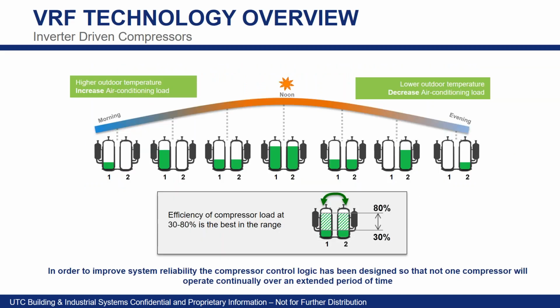Back to where we were here. Okay. Just a simple diagram here of how our compressors are loaded, right? High noon, we're going to be at full load, but then you're going to see as we taper down, we're going to start sharing that load, and that load is going to be shared through our compressors and where we're most efficient. You can see this diagram down here on the bottom. 30 to 80% is our sweet spot, and that's where our factory controls are going to try to keep our compressors running, because that's where we're most efficient.